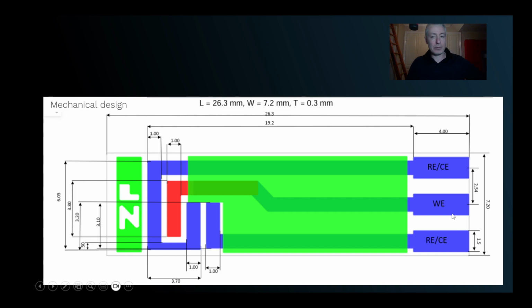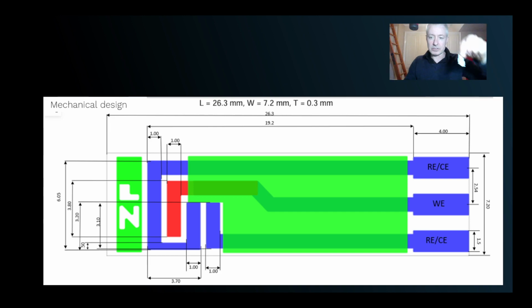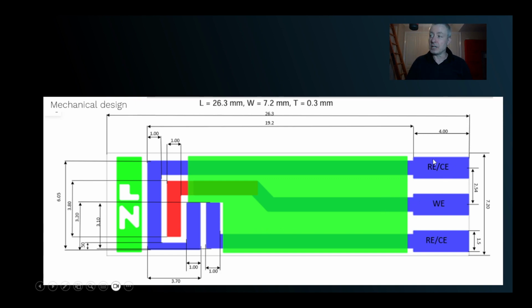The video that I'm using at the moment will be a little bit small, but on the SenseItAll platform, if I click it apart here, we have under here some gold pins, and those gold pins come down and make electrical contact. So it's important that you follow the design rules, because there are some connectors here. I'll put my mouse here. Treat this one as your reference electrode, treat this one as your working electrode, and treat this one as your counter electrode. So have the length, width, and thickness, 26.3 millimeters, 7.2, and 0.3 millimeters respectively. And then lay it out so that the reference electrode is here, the working electrode is in the middle, and the counter electrode is here.